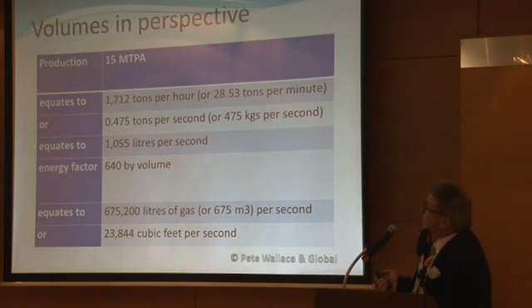A 15 million tonne per annum plant equates to 1,712 tonnes per hour, and that's of liquefied natural gas. That's 475 kilograms per second, which equates to 1,055 litres per second. Because it has an energy factor of 640 for gas, you've then got to multiply that, which equates to 675 cubic metres of gas going through the plant at any one time. You must be able to flare that. You must be able to get rid of that gas. The only way we know of doing it is to incinerate it, and we do that by putting it through a flare.